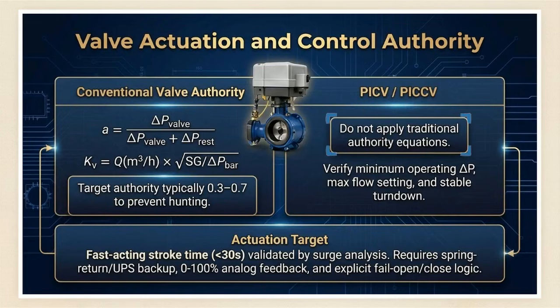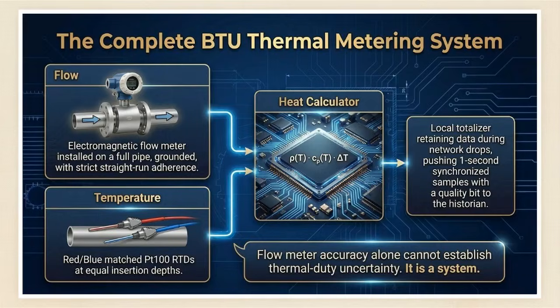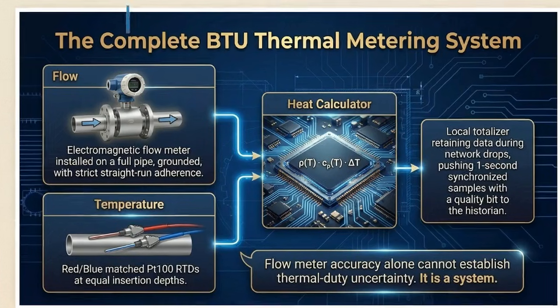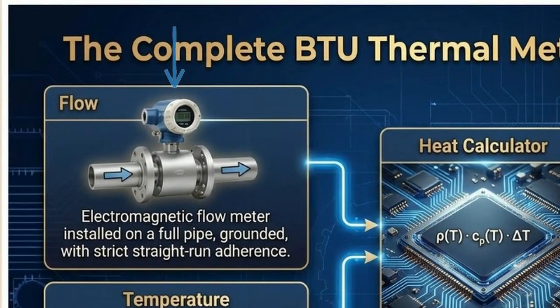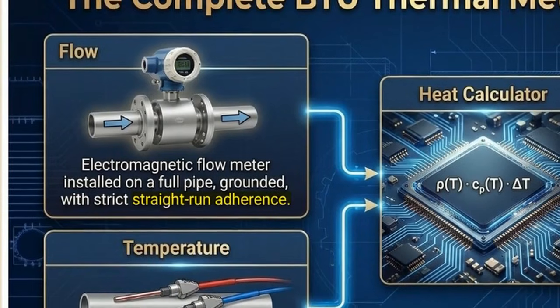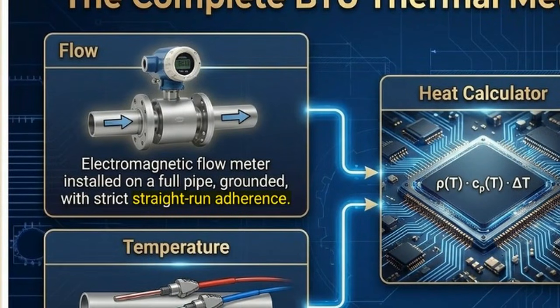When using pressure-independent control valves, you do not apply traditional authority equations. Instead, engineers must verify minimum operating differential pressure and ensure stable flow turndown. This schematic shows a complete BTU thermal metering system. Capturing certifiable thermal duty begins on the left, with an electromagnetic flow meter installed on a completely full pipe. The meter must be properly grounded, demanding strict adherence to specified straight-run lengths of piping.